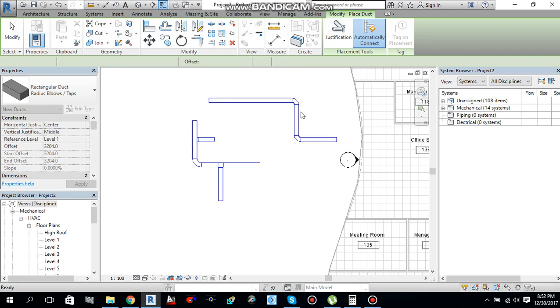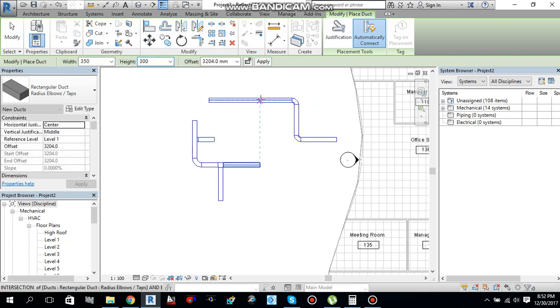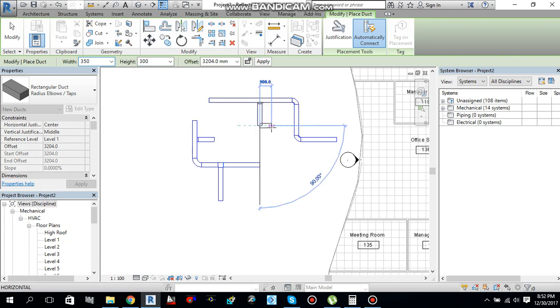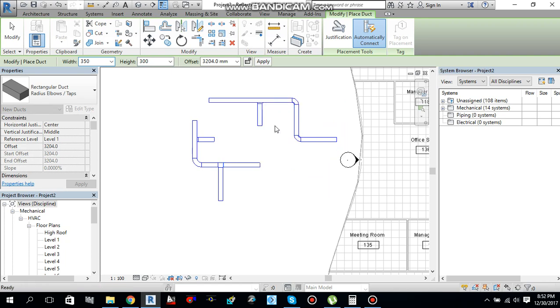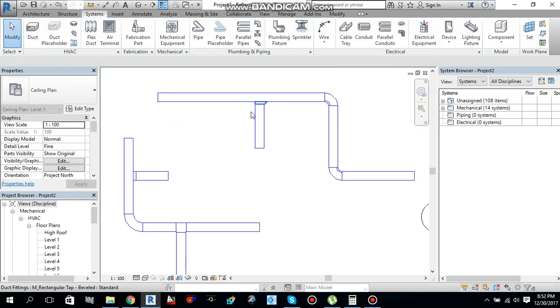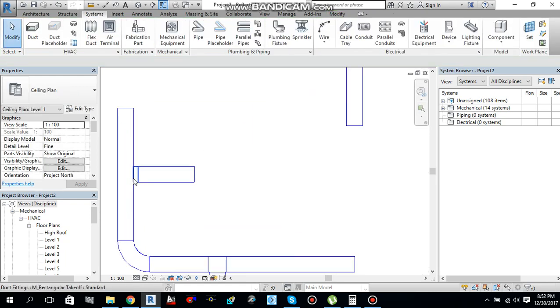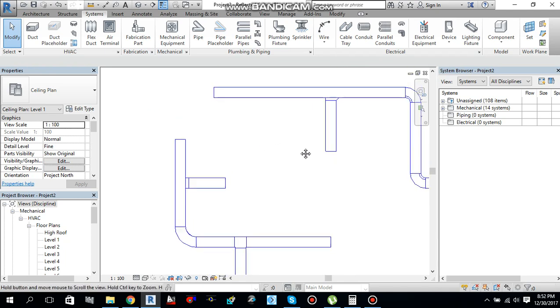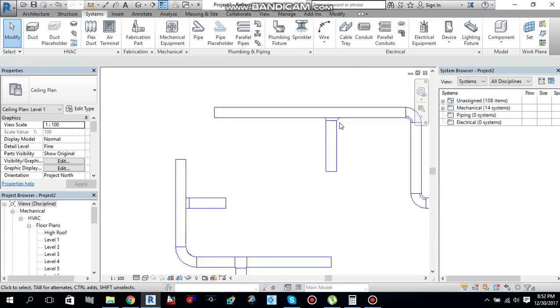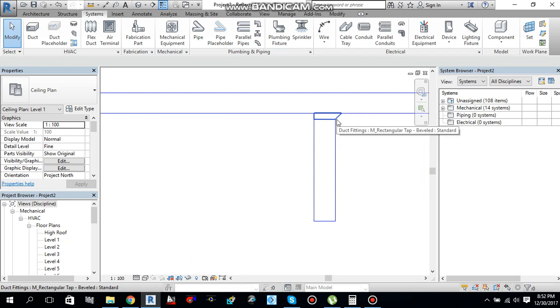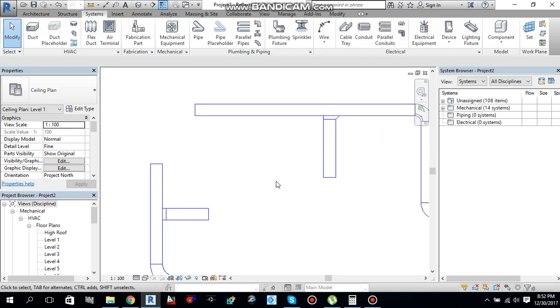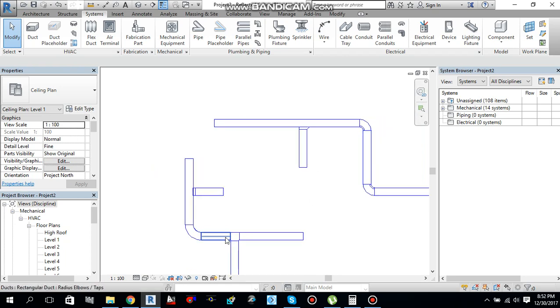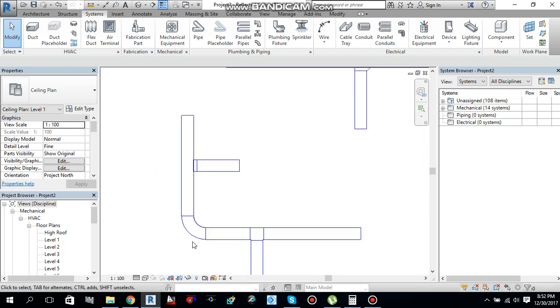Press escape once. Draw a branch from here to here. And press escape twice to cancel the command. And now you can see that this takeoff over here is rectangular standard takeoff. Since I changed routing preferences, so it changed to be a beveled standard takeoff instead of this standard takeoff.